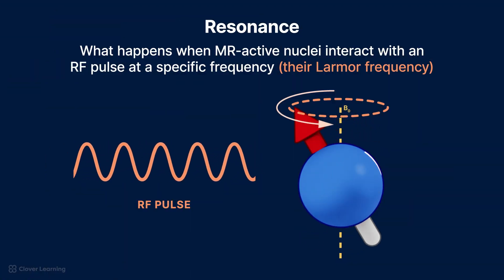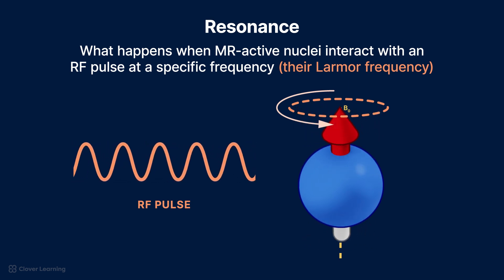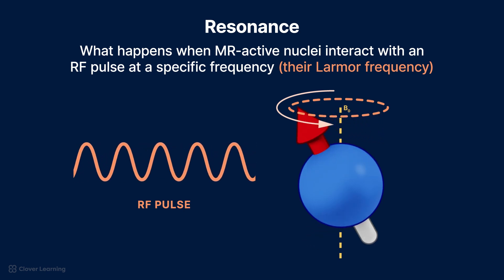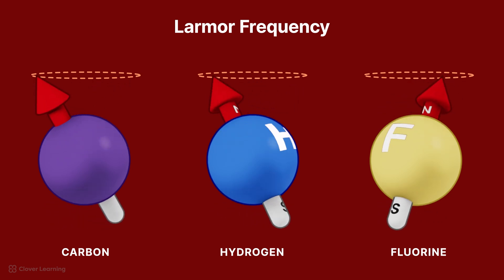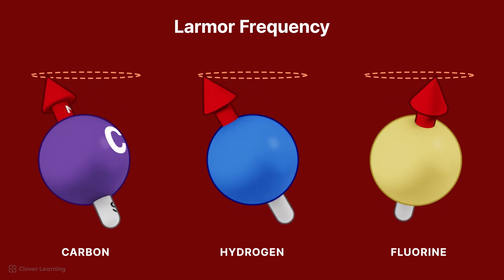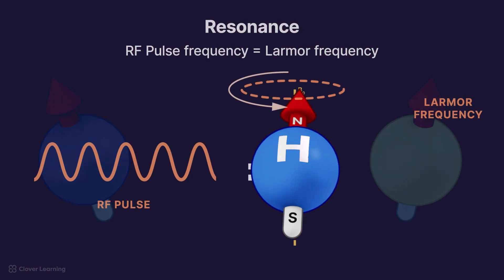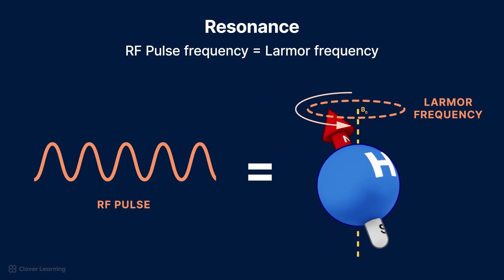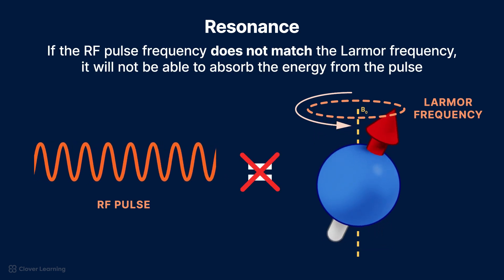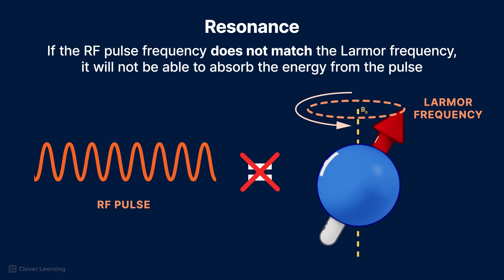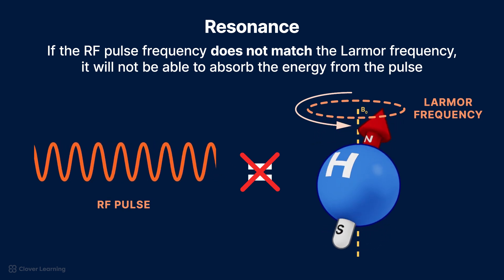First, let's define resonance. In MRI, resonance is what happens when MR-active nuclei interact with an RF pulse at a specific frequency — namely, their Larmor frequency. Remember that each MR-active nucleus has its own unique Larmor frequency, and in MRI we primarily focus on hydrogen nuclei. Hydrogen nuclei will only experience resonance if the RF pulse has a frequency equal to the Larmor frequency of hydrogen. If the RF pulse frequency does not match the hydrogen nuclei's Larmor frequency, it will not be able to absorb the energy from the pulse.